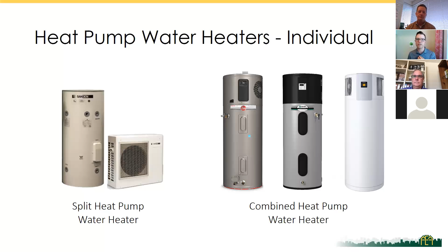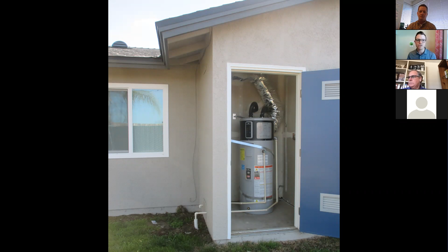This one shows it being ducted. You can duct them, but you don't need to. In fact, for this unit, I think a cheaper solution would have been to fully louver that door you see, and not even bother ducting the heat pump. Just specify a different door with more louvers, then you don't have to duct it, and it's totally fine. So that's an example of an outdoor-like closet location install.